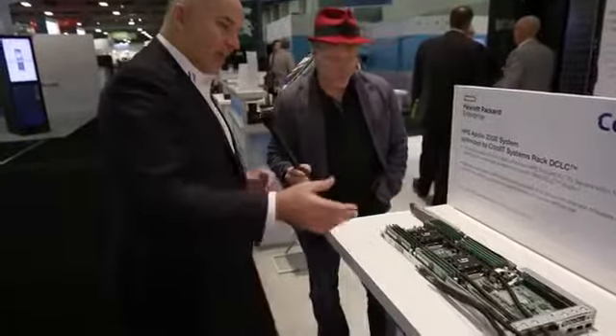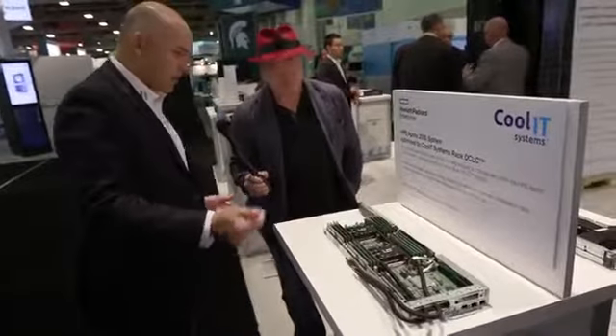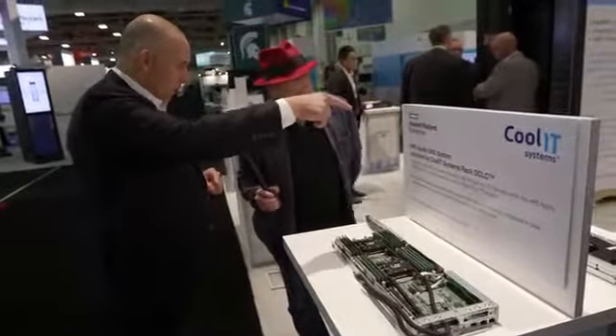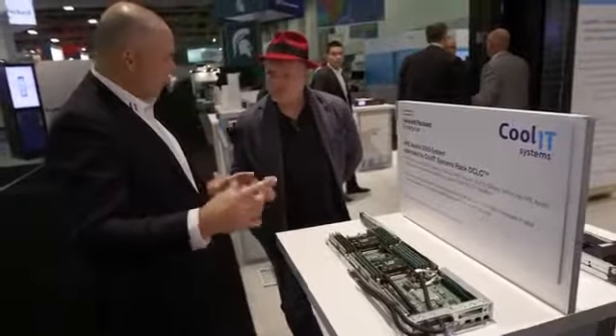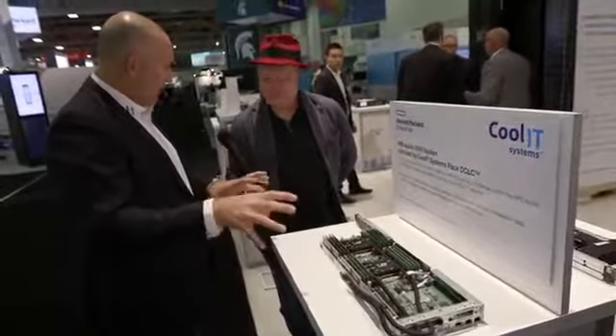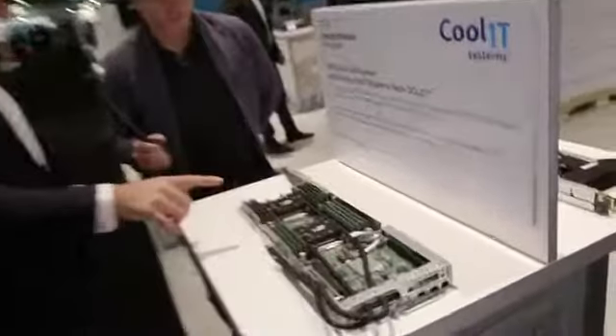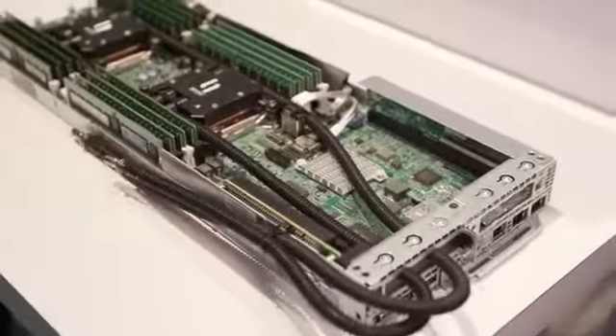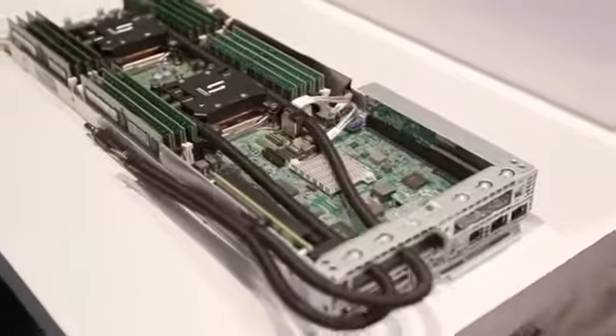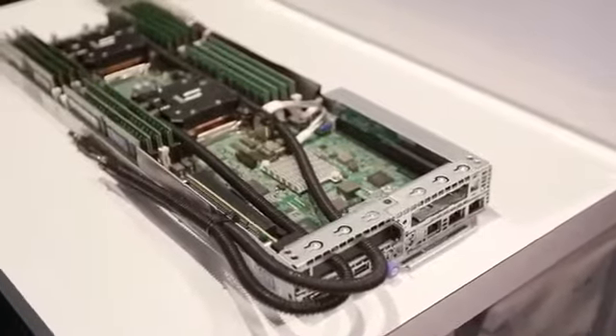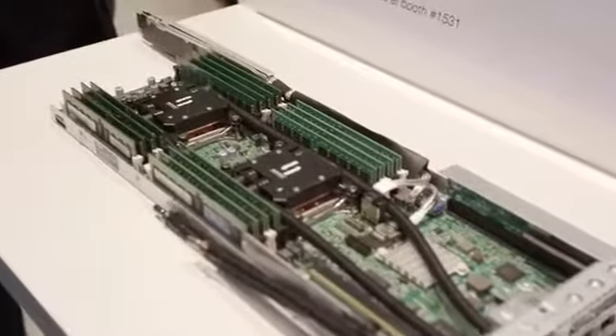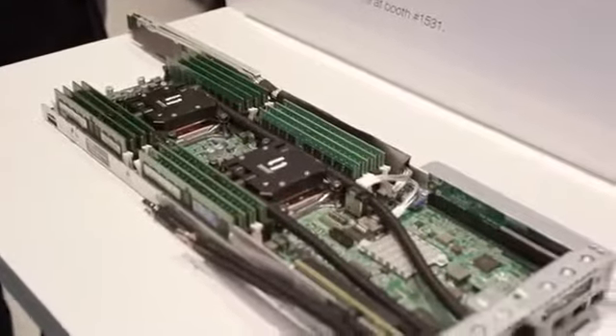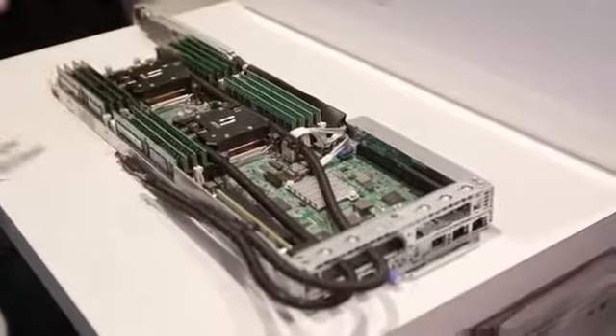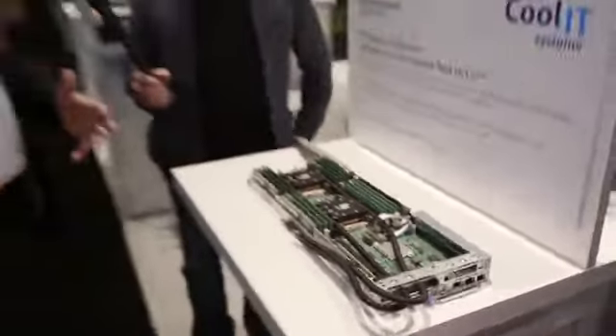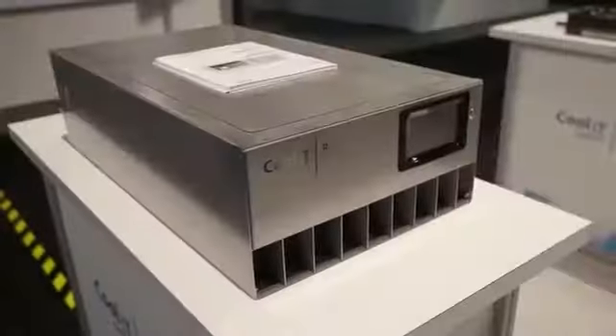Also with HPE, on the same Apollo 2000 platform, we have a manifolded solution. Whereas the other one put all the cooling into one CDU internal to the blade, this one hooks up to the manifold on the outside of the system, enabling that chip-to-atmosphere path. The heat starts in the CPU, goes out to the manifold, then to our heat dissipation solutions, which we'll look at next.